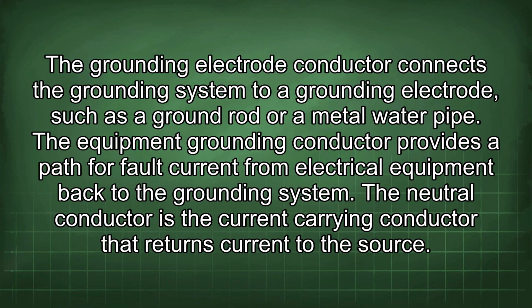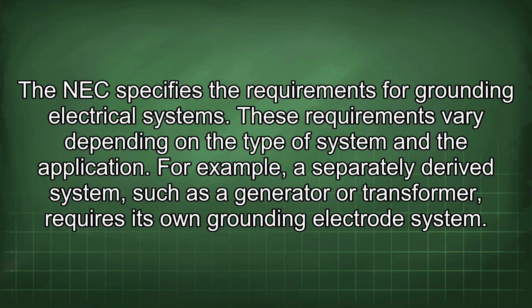The grounding electrode conductor connects the grounding system to a grounding electrode, such as a ground rod or a metal water pipe. The equipment grounding conductor provides a path for fault current from electrical equipment back to the grounding system. The neutral conductor is the current-carrying conductor that returns current to the source. The NEC specifies the requirements for grounding electrical systems. These requirements vary depending on the type of system and the application. For example, a separately derived system, such as a generator or transformer, requires its own grounding electrode system.